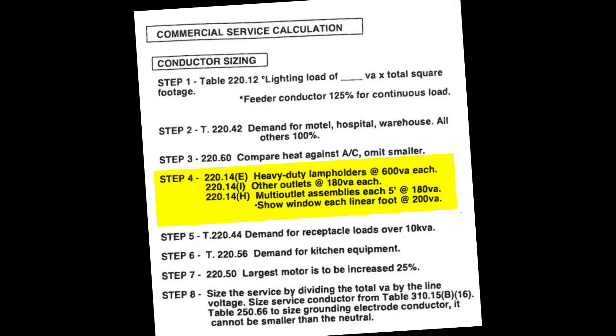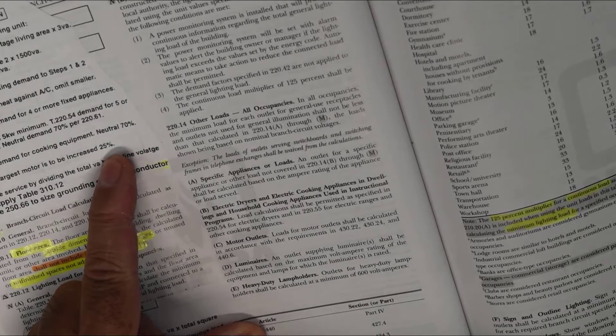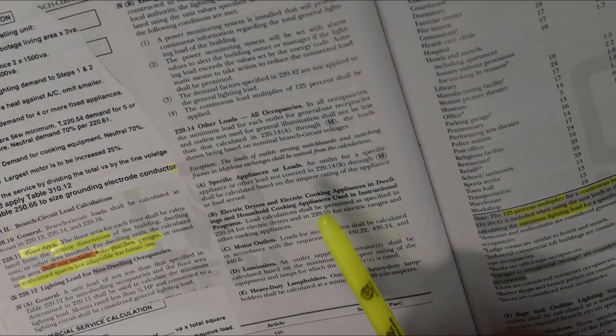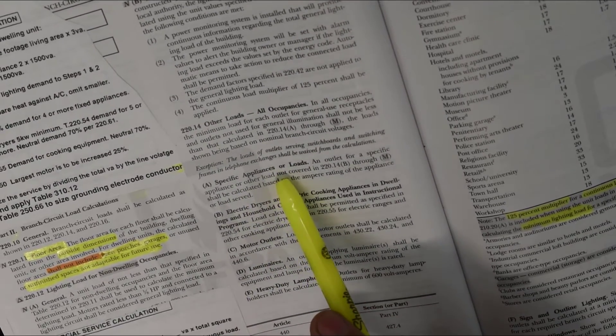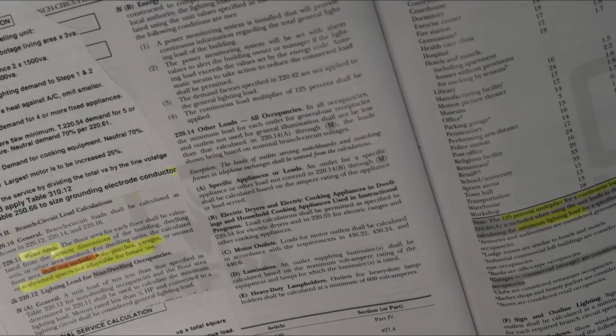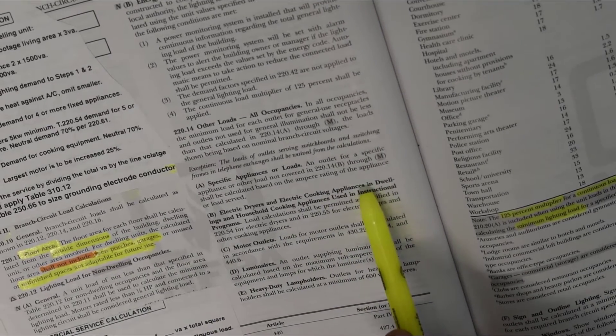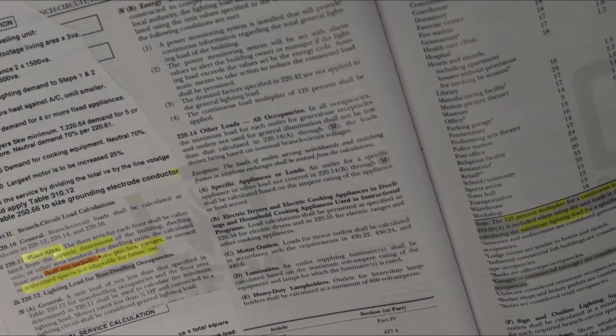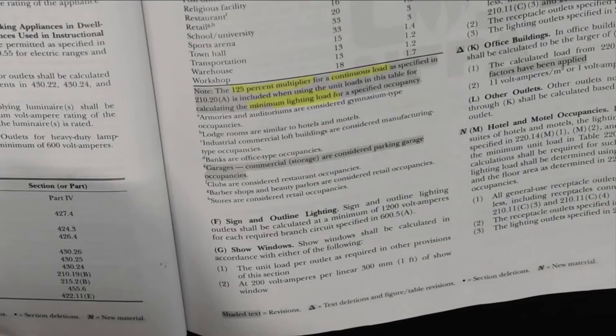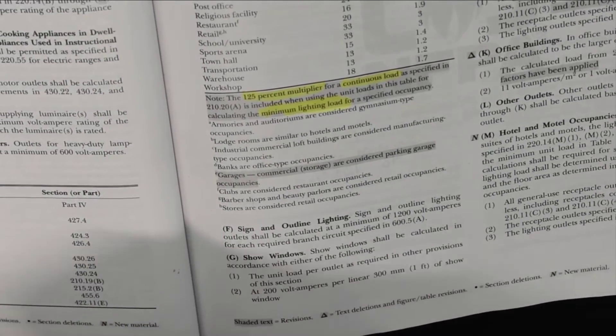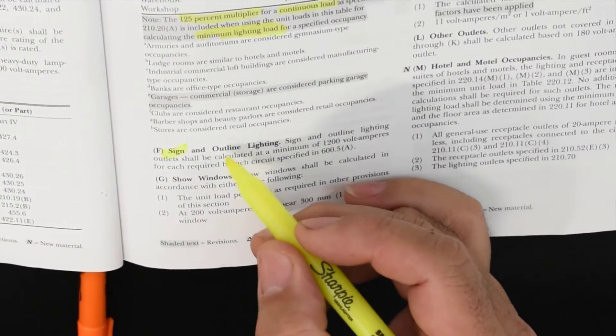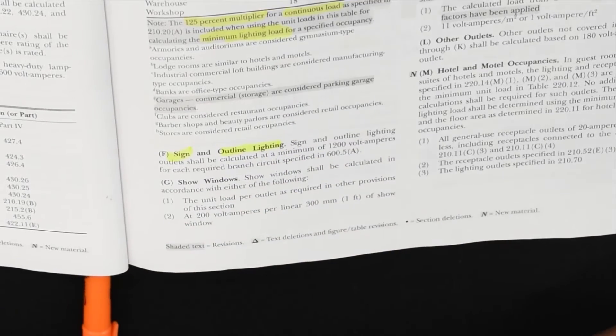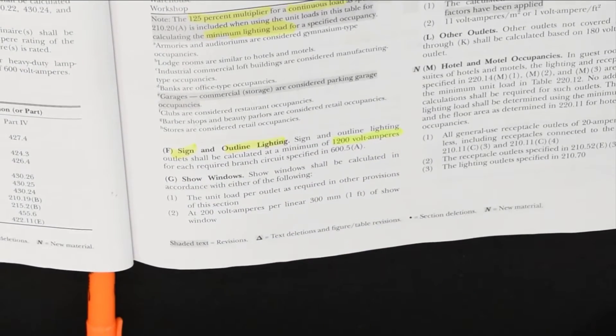Step 4 takes us to 220.14, which covers other loads for all occupancies, sections A through M. Section A covers specific appliances. B is dryers and electric cooking. C is motors. D is luminaires. E is heavy-duty lamp holders. F is signs and outline lighting — the wording on that one tends to confuse people. Signs and outline lighting are calculated at a minimum of 1,200 volt-amps.